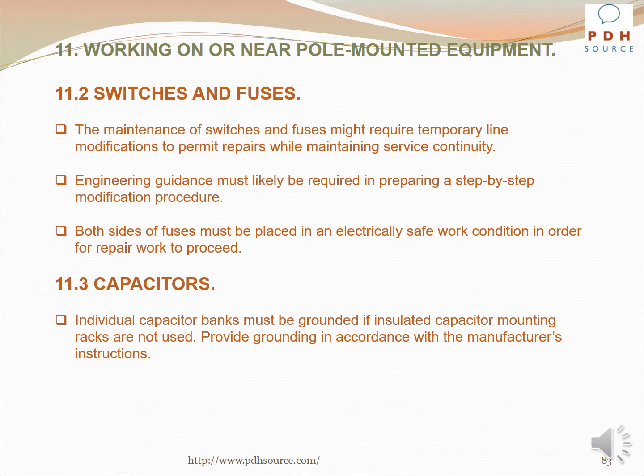The maintenance of switches and fuses might require temporary line modifications to permit repairs while maintaining service continuity. Engineering guidance will likely be required in preparing a step-by-step modification procedure. Both sides of fuses must be placed in an electrically safe work condition in order for repair work to proceed. Individual capacitor banks must be grounded if insulated capacitor mounting racks are not used. Provide grounding in accordance with the manufacturer's instructions.